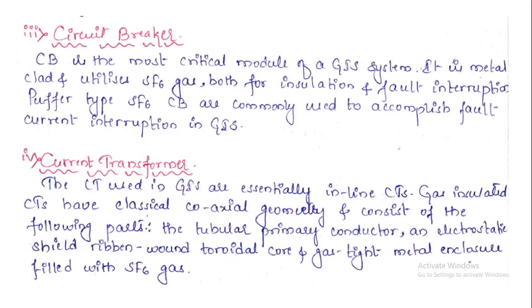Next we have the circuit breaker. The circuit breaker is the most critical module of the GIS system. It is metal clad and utilizes SF6 gas both for insulation and fault interruption. As we already discussed in the types of circuit breakers, SF6 circuit breakers, especially puffer type SF6 circuit breakers, are commonly used to accomplish fault current interruption in the GIS system.